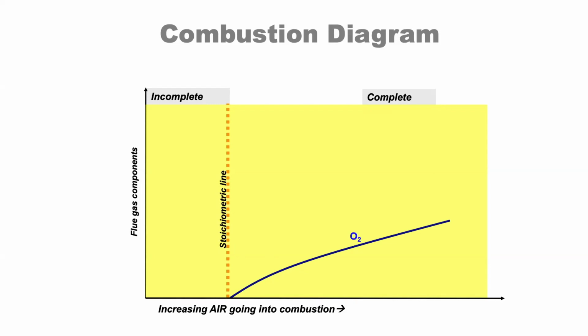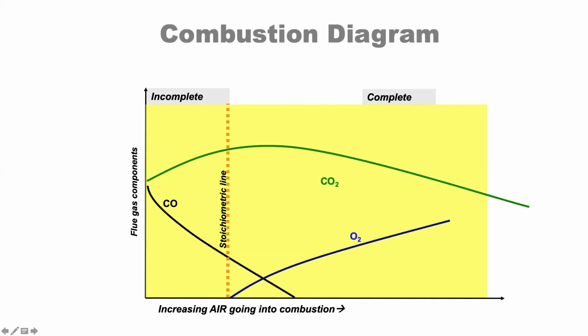So increasing air going into the combustion, you'd see the oxygen number start to appear and start to rise. The CO2 level, there's more air going into combustion, it would start to reach a peak and then drop off due to dilution, whereas the oxygen concentration would increase due to excess air. The carbon monoxide line, generally speaking, decreases, and you're at the point of where you're decreasing the amount of carbon monoxide created. Then after this point, when it reaches the stoichiometric line, you have excess air, it actually starts to dilute the concentration. And then the efficiency peaks about the same point that the CO2 level peaks.